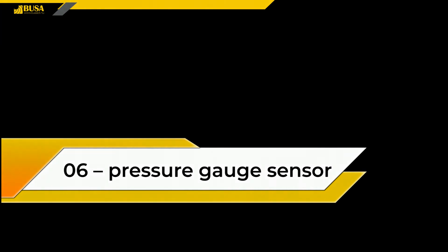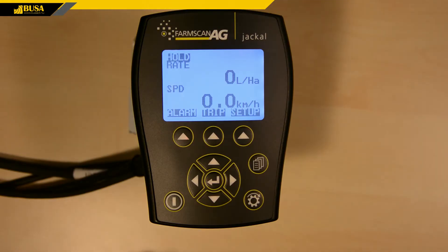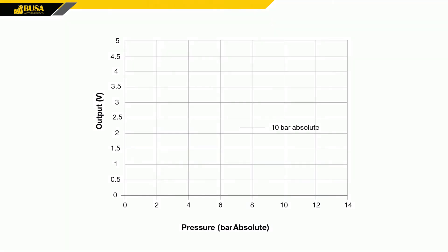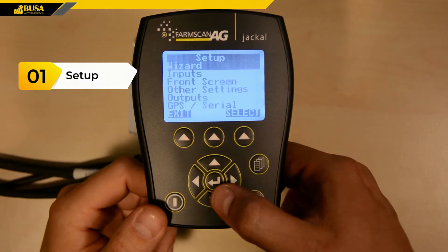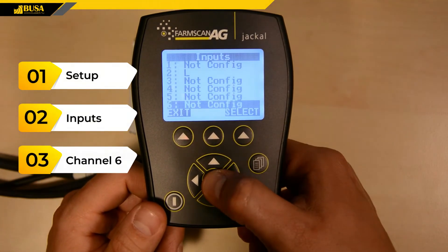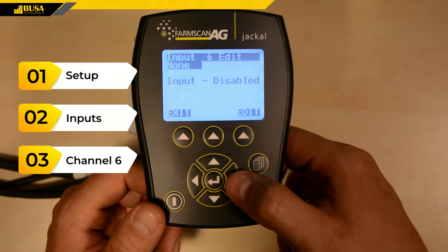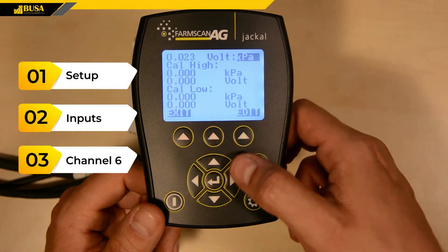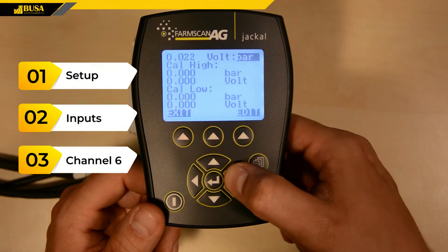A Pressure Gauge Sensor can be hooked up to the pressure input marked 6. The values can be found on the datasheet for the sensor. In our case, the 10 bar sensor at 0 bar pressure gives a signal of 0.5 volts output voltage, whereas 10 bar pressure gives 4.5 volts. In the Setup menu, choose the input item, then Channel 6. Set the units, then the high and low values read off from the calibration datasheet.